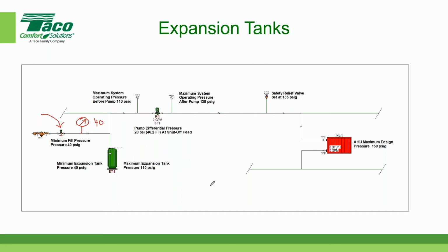Excellent. While you're on this drawing, I want to reiterate that this is one of the most common issues that Rich and I come up with, and others in our industry, with expansion tanks. Before that expansion tank is piped into the system, you need to properly pressurize it. Once you pipe it into the system, it's a pain in the you-know-what to properly pressurize that expansion tank. Correct. Pre-charge the tank to the calculated minimum or fill pressure before you connect it to the system.